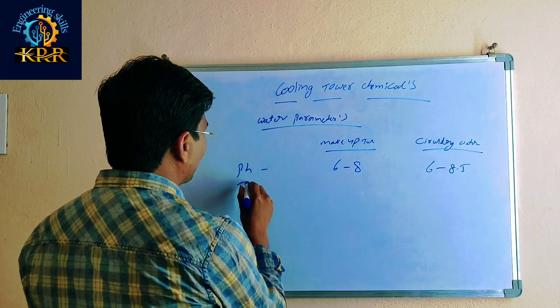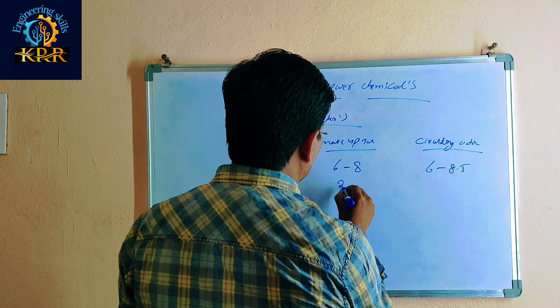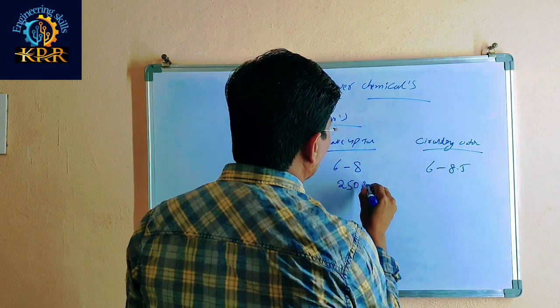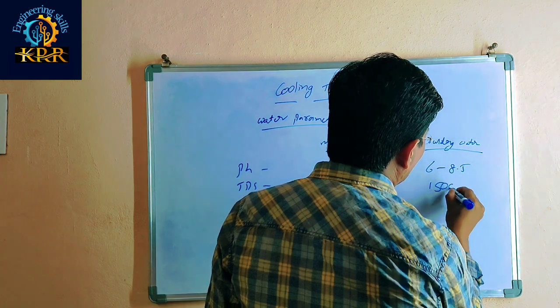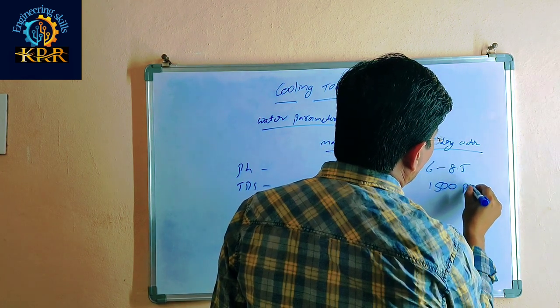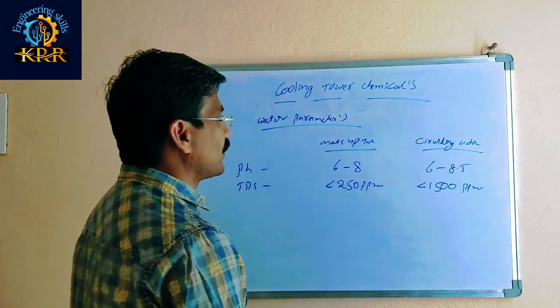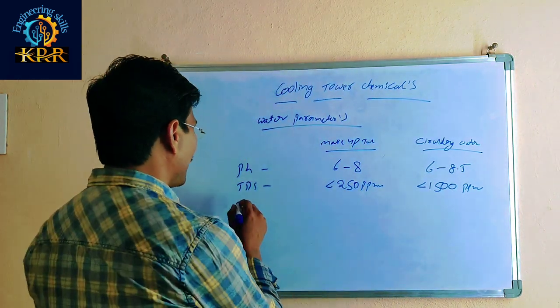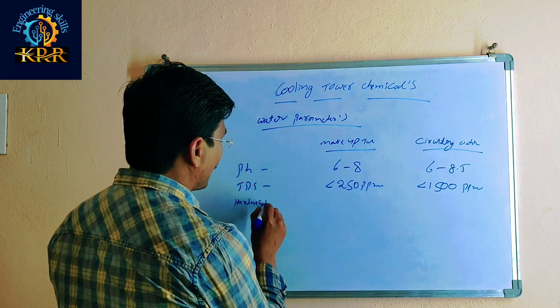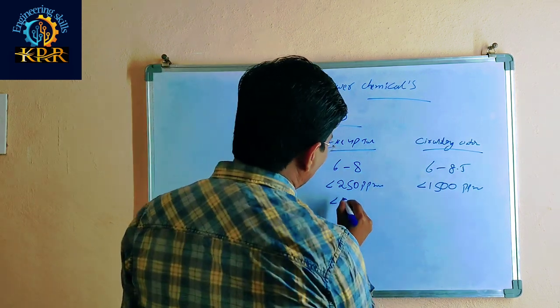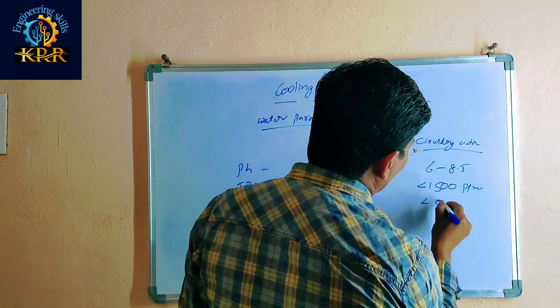For TDS: in makeup water it should be less than or equal to 250 ppm, and in circulation water less than or equal to 1500 ppm. For hardness: in makeup water less than or equal to 50 ppm, and in circulation water less than or equal to 500 ppm.